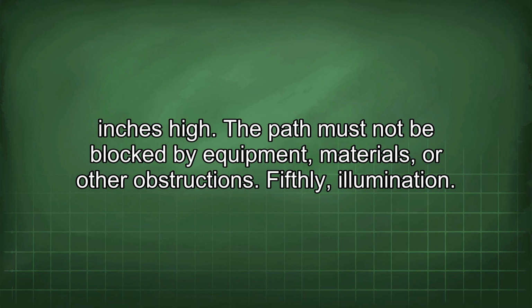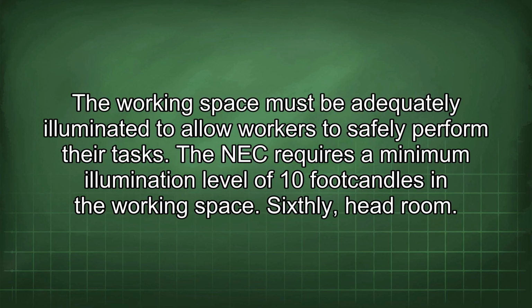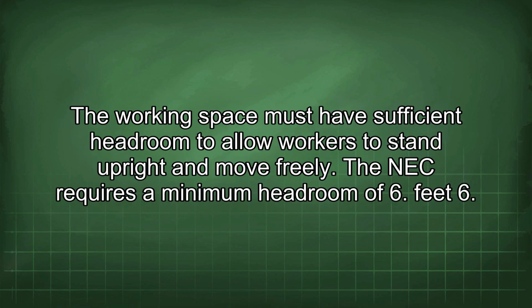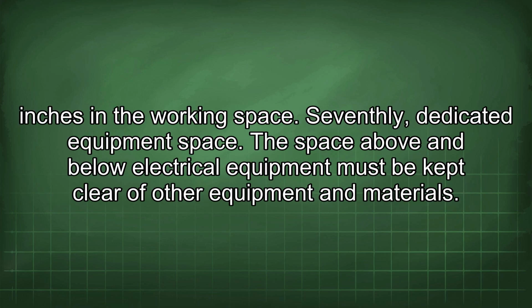Fifthly, illumination. The working space must be adequately illuminated to allow workers to safely perform their tasks. The NEC requires a minimum illumination level of 10 footcandles in the working space. Sixthly, headroom. The working space must have sufficient headroom to allow workers to stand upright and move freely. The NEC requires a minimum headroom of 6 feet 6 inches in the working space.